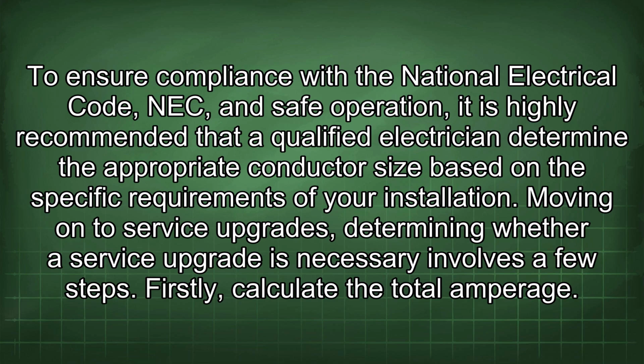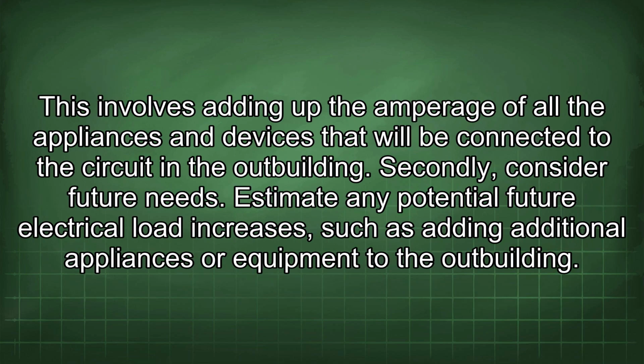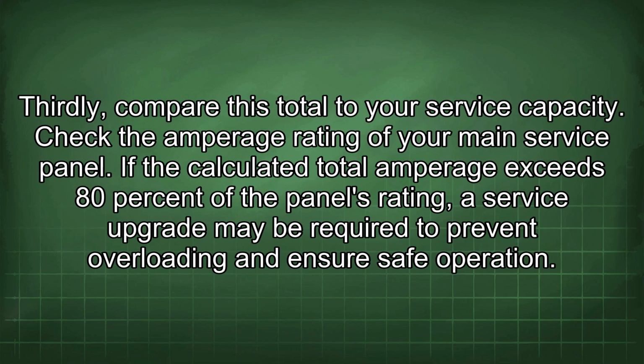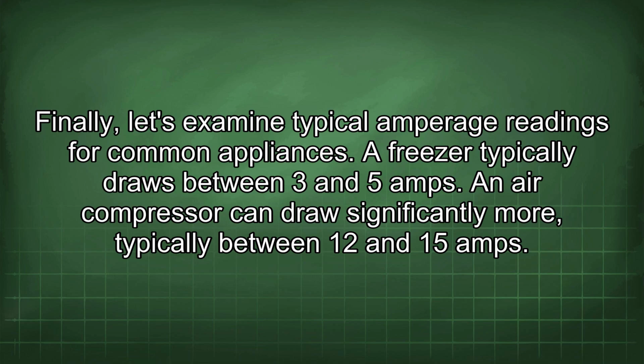Moving on to service upgrades, determining whether a service upgrade is necessary involves a few steps. Firstly, calculate the total amperage. This involves adding up the amperage of all the appliances and devices that will be connected to the circuit in the outbuilding. Secondly, consider future needs. Estimate any potential future electrical load increases, such as adding additional appliances or equipment to the outbuilding. Thirdly, compare this total to your service capacity. Check the amperage rating of your main service panel. If the calculated total amperage exceeds 80% of the panel's rating, a service upgrade may be required to prevent overloading and ensure safe operation.